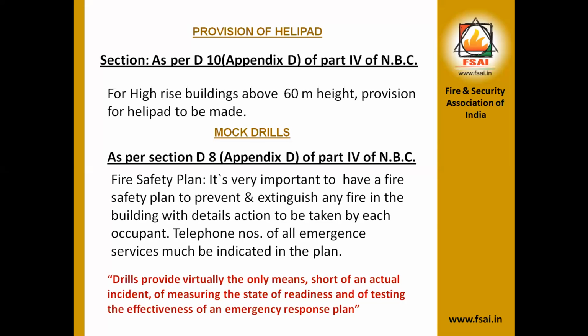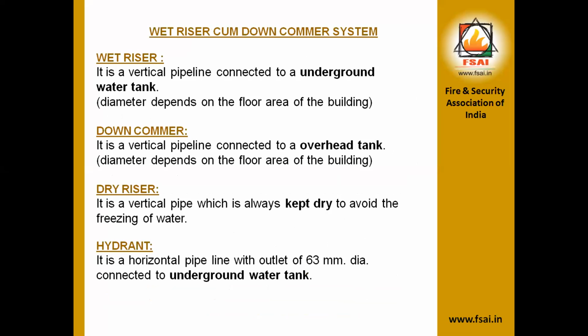We can understand some basic concepts of wet riser, downcomer, dry riser and hydrant. So what is a wet riser? It is a vertical pipeline connected to the underground water tank. Downcomer, it is a vertical pipeline connected to the overhead tank. Dry riser, it is an alternative provision which is used in case of emergency to avoid the freezing of water. Hydrant, it is a horizontal pipeline with outlet of 63 mm diameter connected to the underground water tank.